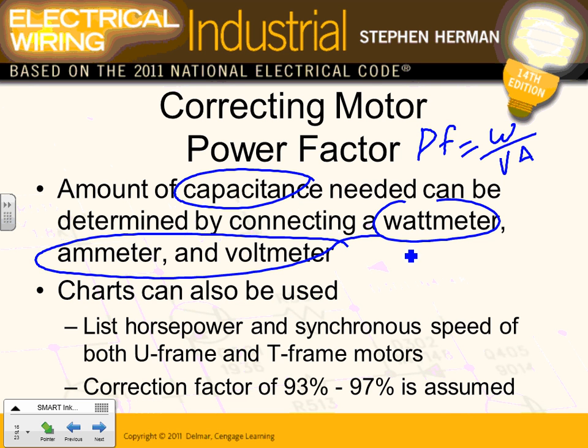Summarize. We can correct power factor with synchronous machines or with capacitors. For motors, you can correct the power factor, guys, in two ways. You can correct them by adding capacitors at the switchgear or by adding them to the motors directly, the offenders. Motors have two types when they design them. In the old times, they used U-frame motors. They started using T-frame motors. Based on what type of frame for these motors, it decides what size capacitor to offset the work of these motors. The reason why we care about motors is because motors are the biggest offenders when it comes to low power factor.